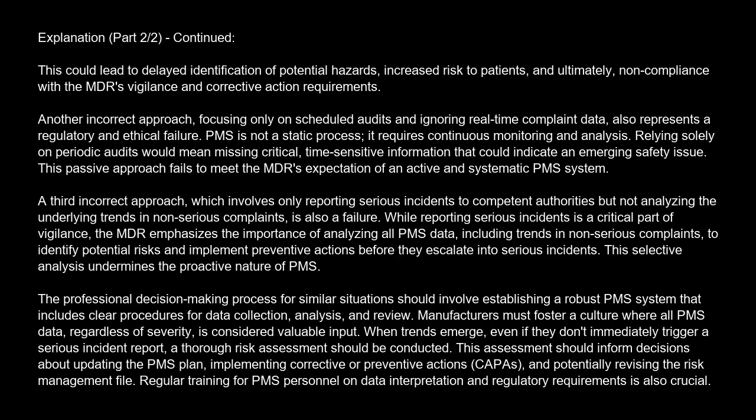This selective analysis undermines the proactive nature of PMS. A professional decision-making process for similar situations should involve establishing a robust PMS system that includes clear procedures for data collection, analysis, and review. Manufacturers must foster a culture where all PMS data, regardless of severity, is considered valuable input. When trends emerge, even if they don't immediately trigger a serious incident report, a thorough risk assessment should be conducted.